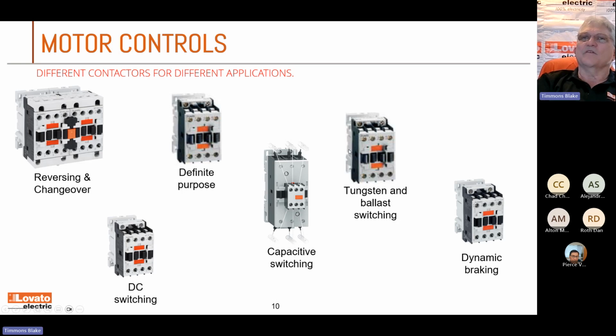And then we have some other contactors, and you'll see in the back of our catalog all these different lighting categories. Back to those AC categories I mentioned earlier: what kind of current are you using? Now you have them for tungsten, ballast switching, dynamic braking. That's what you're doing with a VFD. That's going to be some DC current, which you've got to break. A lot of those poles have to be wired in series. Okay, and DC switching, kind of the same thing.